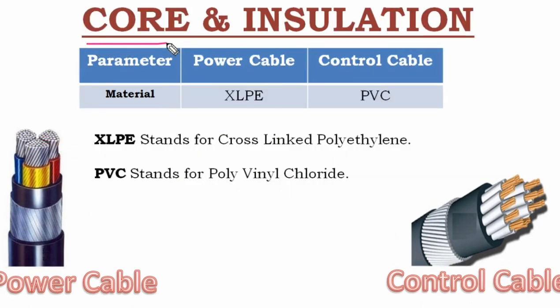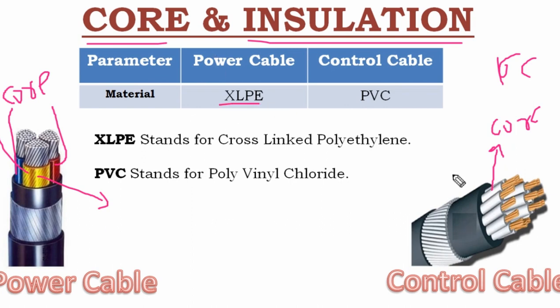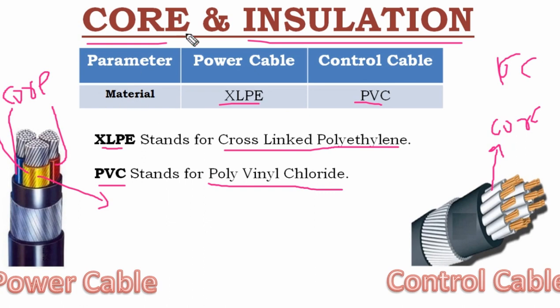Now we will learn about the core and insulation. In the power cable, there are 3 cores identified by the colors red, yellow, and blue. In the control cable, there are 16 cores, all gray in color. The insulation material used in the power cable is XLPE — Cross-Linked Polyethylene — and in the control cable, PVC — Polyvinyl Chloride — is used.